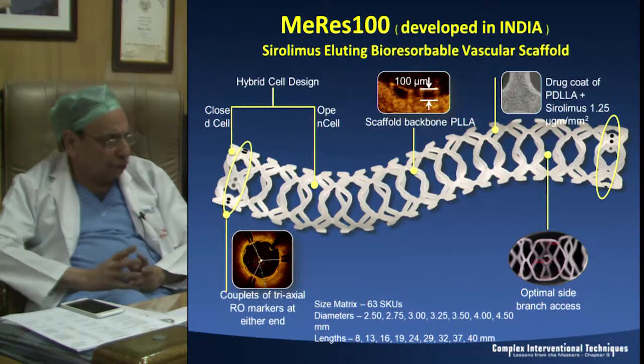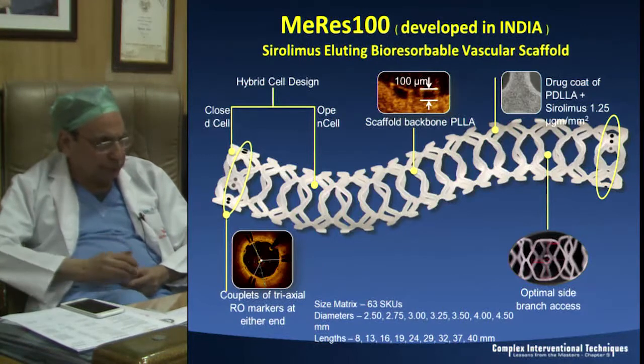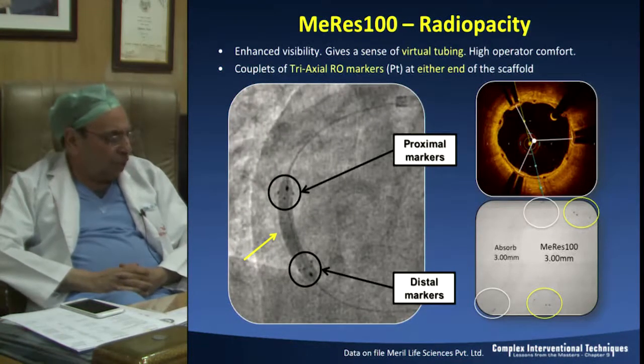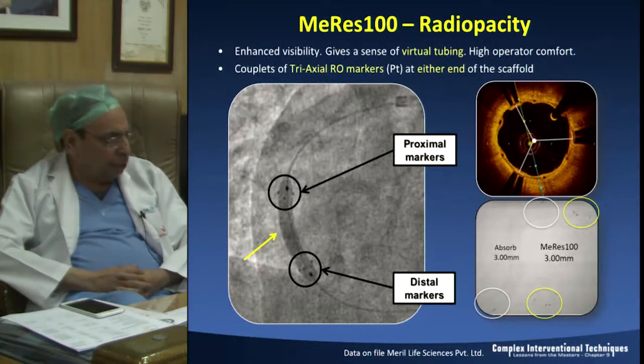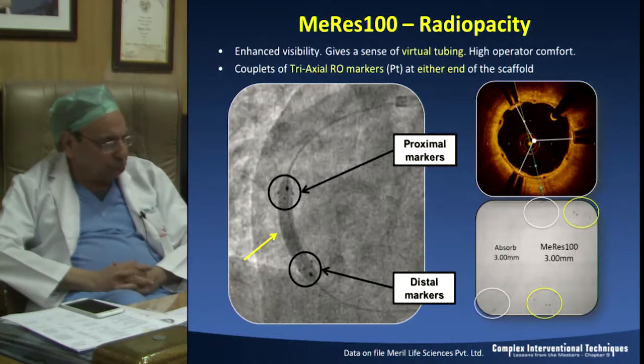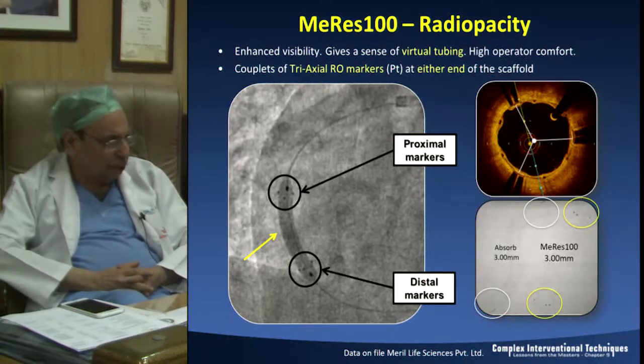There are 63 sizes available, with diameters from 2.5 to 4.5mm and lengths from 8mm to 40mm in 3 to 5 millimeter increments. The opacity of the markers is really remarkable - you can see them so well that it appears like a virtual tubing, giving operators a much better comfort, especially those who have used Absorb, as you can see the scaffold in three dimensions.